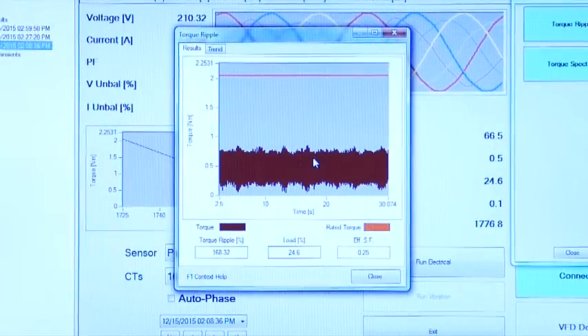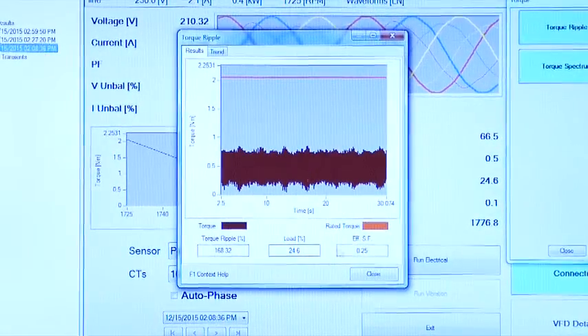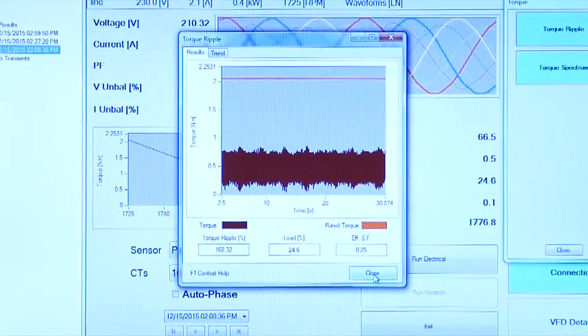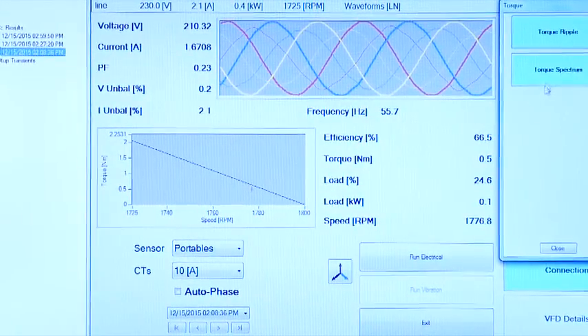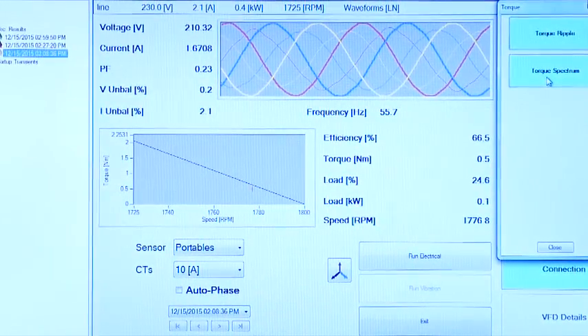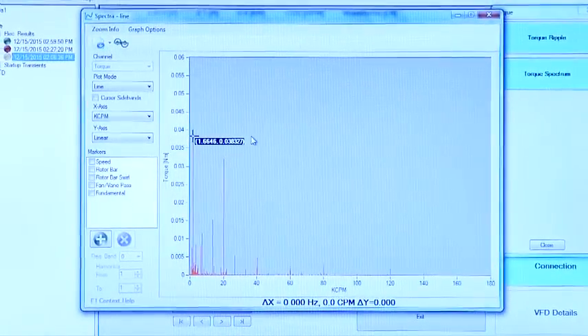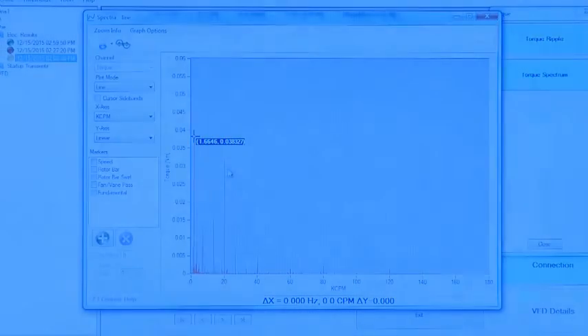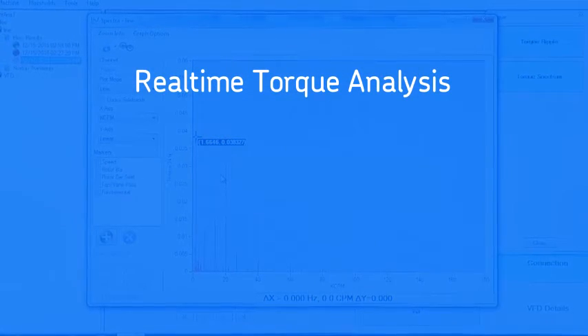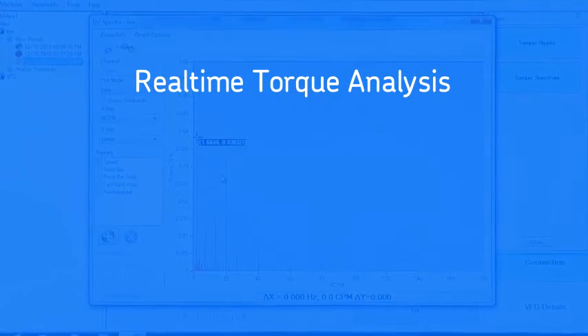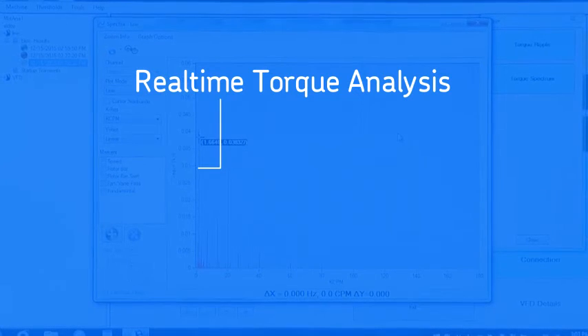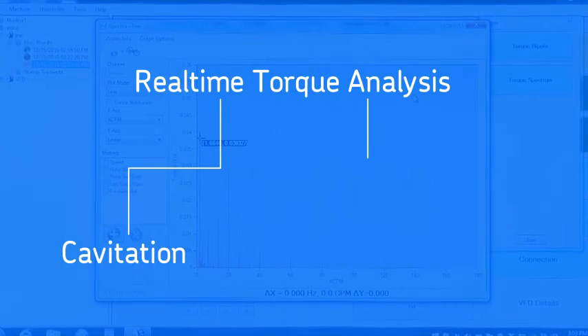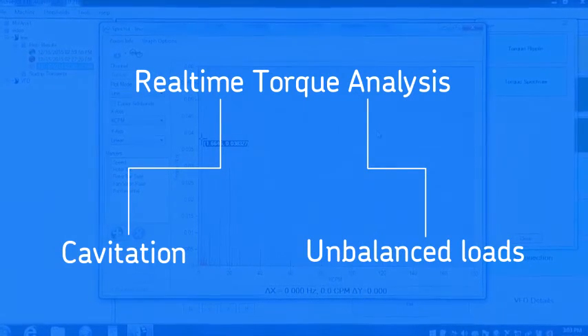The load performance is analyzed by looking at the motor torque output. The output torque required is determined by the load. SKF dynamic motor analyzers allow you to look at the load torque in real time to find even temporary overload conditions or machine faults, such as cavitation or unbalanced loads.